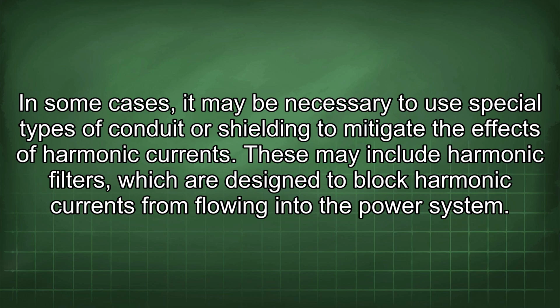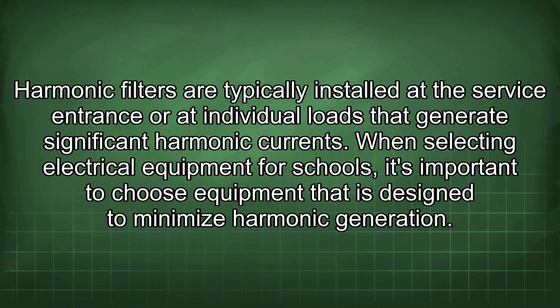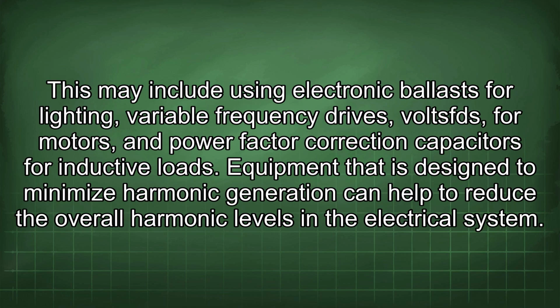These may include harmonic filters, which are designed to block harmonic currents from flowing into the power system. Harmonic filters are typically installed at the service entrance or at individual loads that generate significant harmonic currents. When selecting electrical equipment for schools, it's important to choose equipment that is designed to minimize harmonic generation. This may include using electronic ballasts for lighting, variable frequency drives for motors, and power factor correction capacitors for inductive loads. Equipment that is designed to minimize harmonic generation can help to reduce the overall harmonic levels in the electrical system.